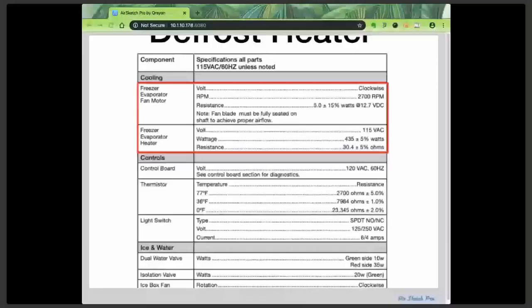The reason is that the component may read good under ohms but start what we call failing under load when electrons start blasting through it. Those electrons traveling through the component, wires, or connectors to that load can cause it to fail under load because they create heat. Heat creates expansion in metal, and anything that tends to separate will do so. So the dead, surefire way is to test all your AC loads under load, and to do that you'd want to measure amps.